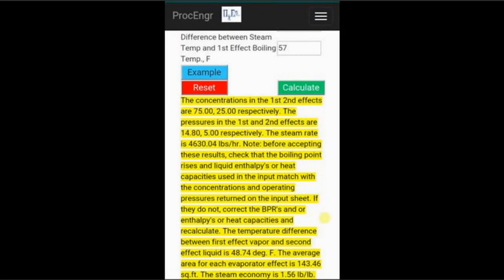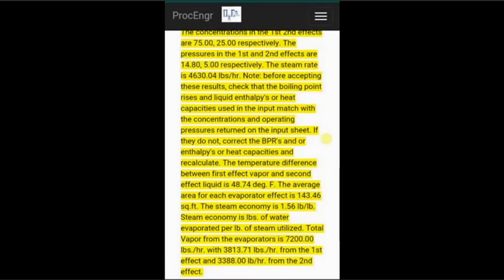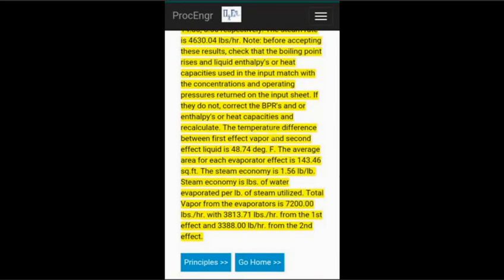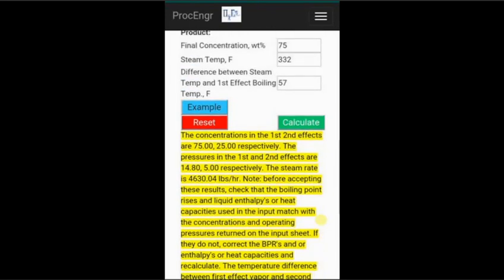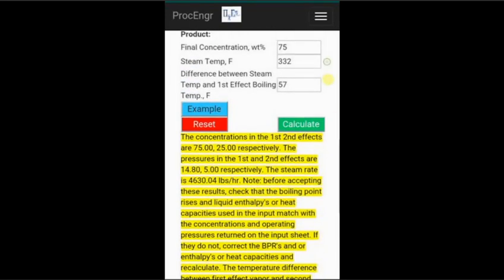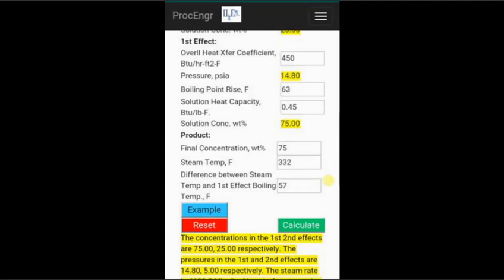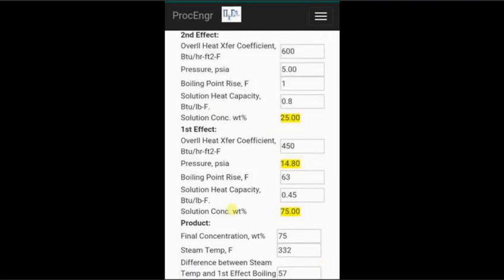We see for this case, the steam consumption is 4,630 pounds per hour. The difference in temperature between effects is 48.74 degrees Fahrenheit. The average area of each evaporator is 143.46 square feet. The steam economy is 1.56 pounds of water evaporated per pound of steam utilized. And the total amount of evaporation is 7,200 pounds per hour, with 3,813 coming from the first effect and the balance coming from the second effect.